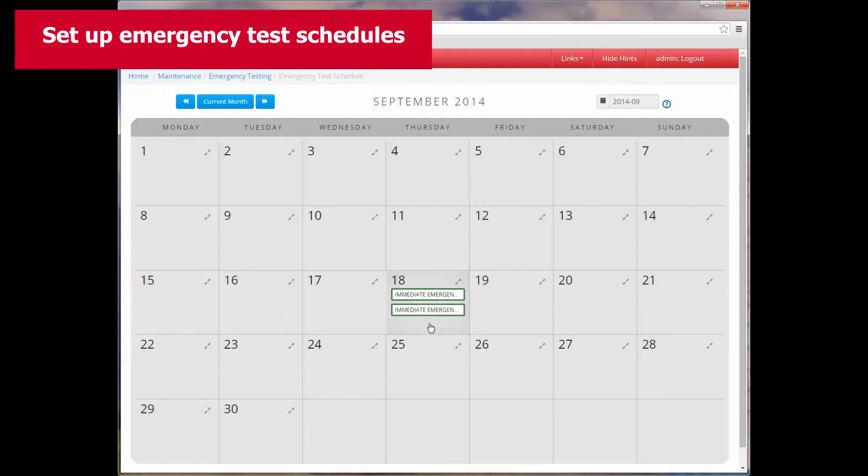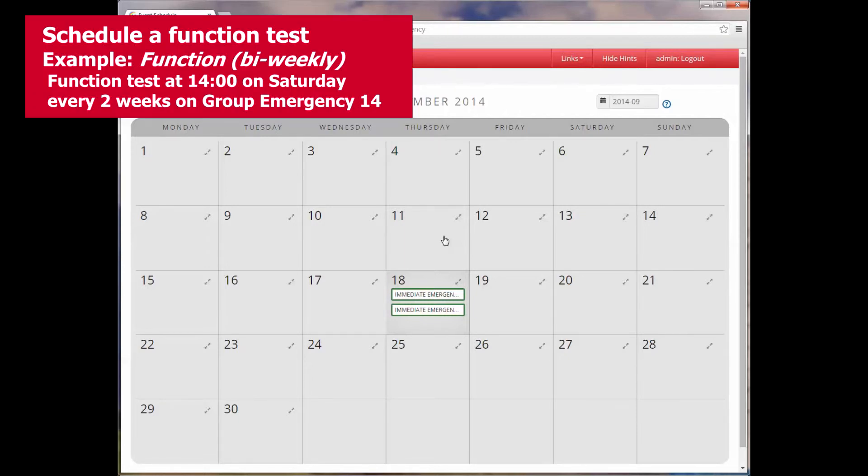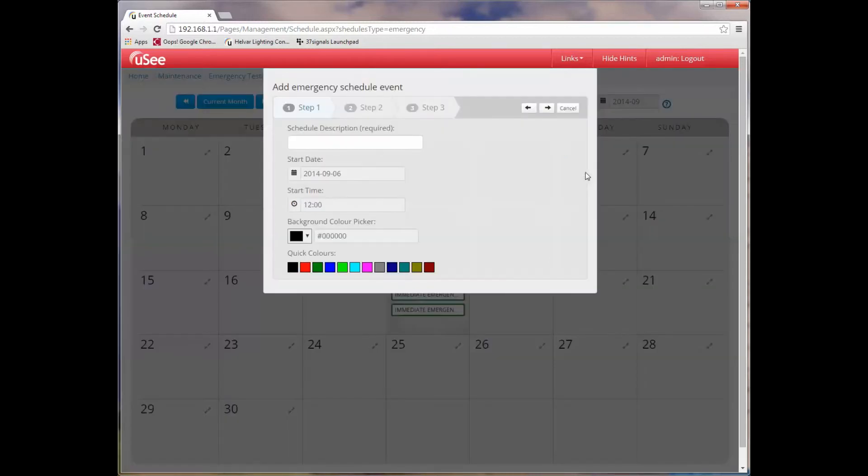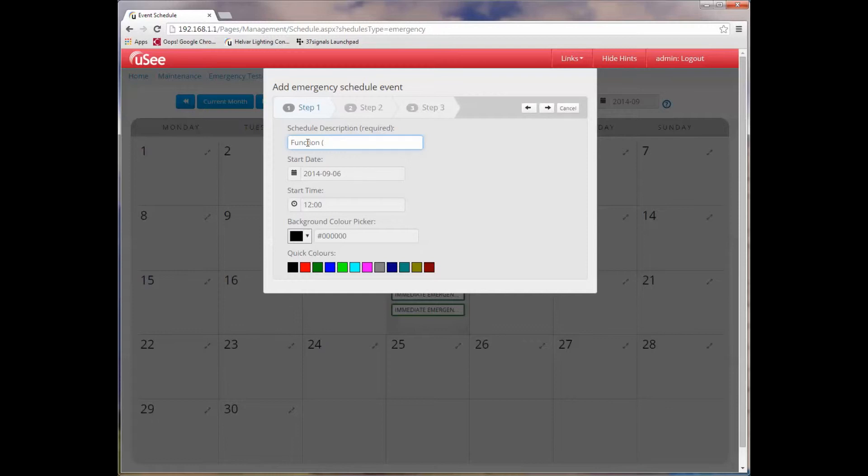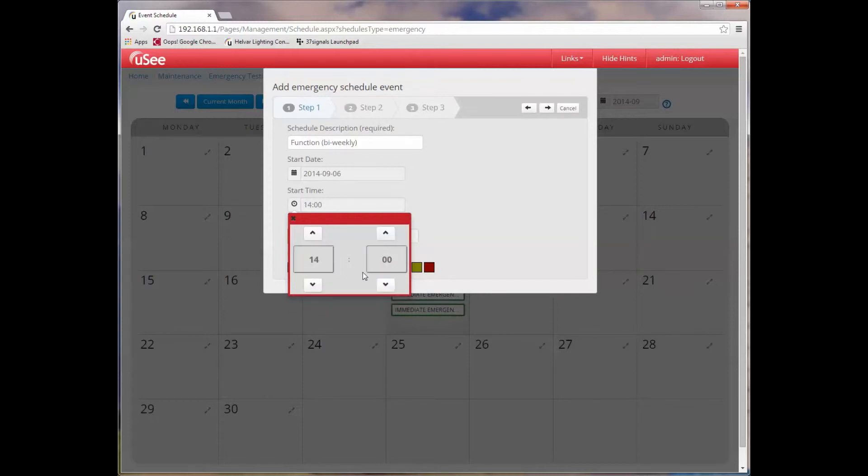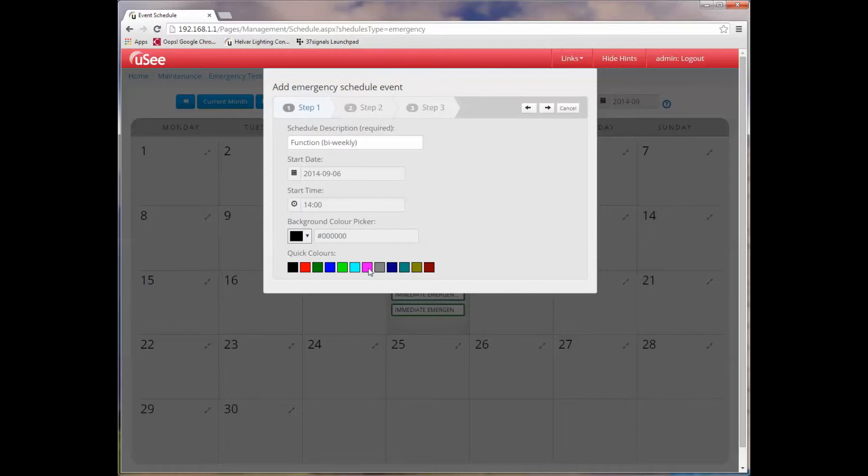So let's actually set up some emergency test schedules. I want to schedule my emergency test so it doesn't disturb people in the office environment. So let's start off by arranging a repetitive function test which will take place out of office hours. I'm going to start by selecting a Saturday within the month. I'm going to give this emergency schedule a meaningful name. I'm going to call it function, and I'm going to put in brackets it's bi-weekly. I've already got my start date as the Saturday. And because I don't expect people to be in the office on a Saturday afternoon, I can safely start this test at 2 o'clock in the afternoon. I'll give it a background color. In fact, we'll just use one from the picker, a quick pick color.